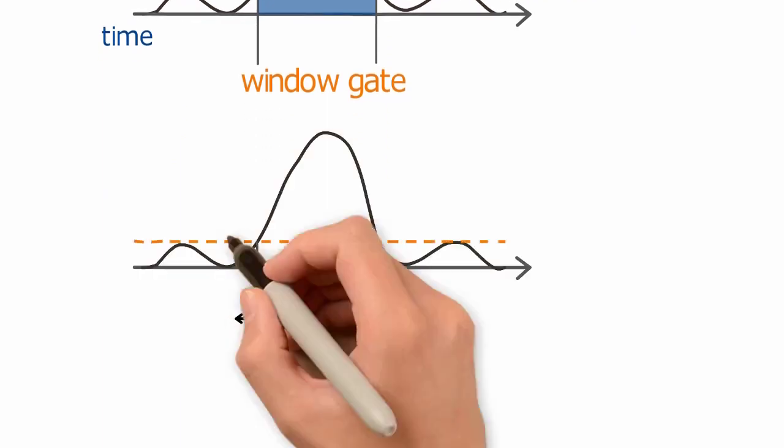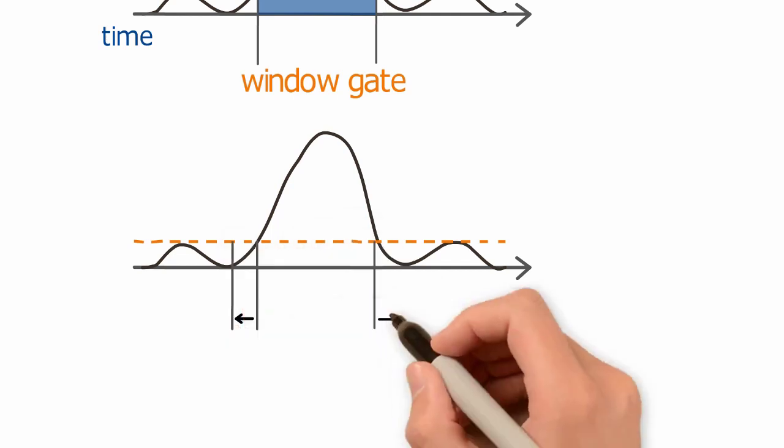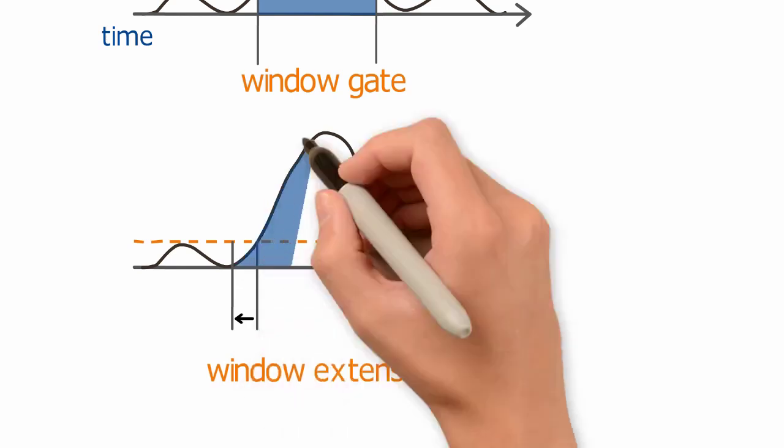To measure the complete area of the voltage pulse, the window gate can be extended by a set amount of time. This is the window extension. The window extension will be applied to the window gate any time a signal crosses threshold, which allows the system to accurately measure the total area of the voltage pulse.